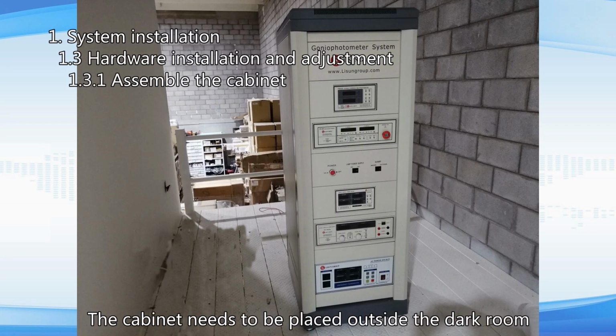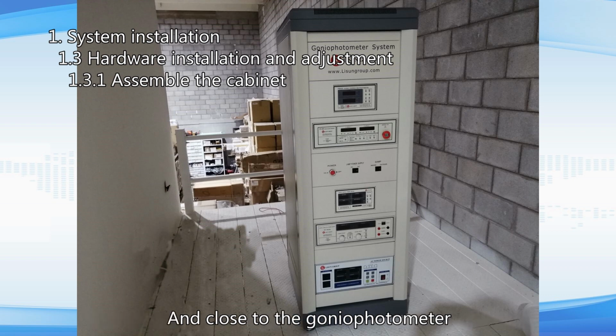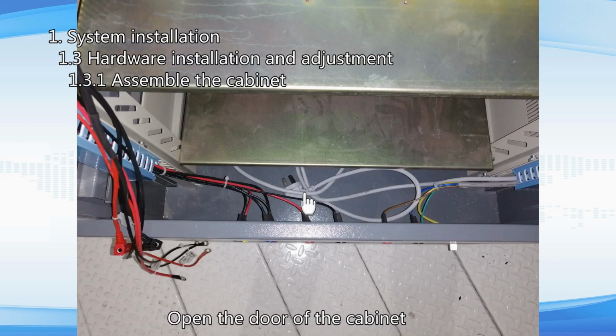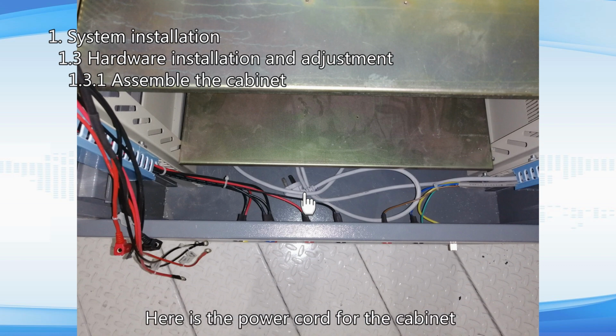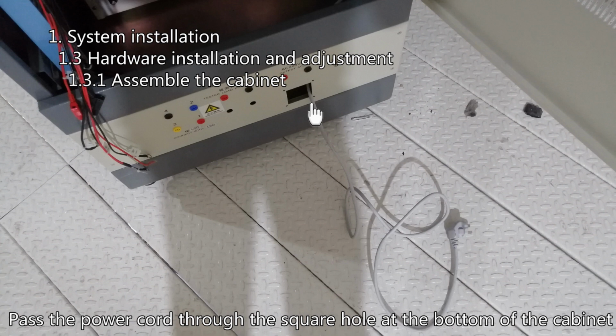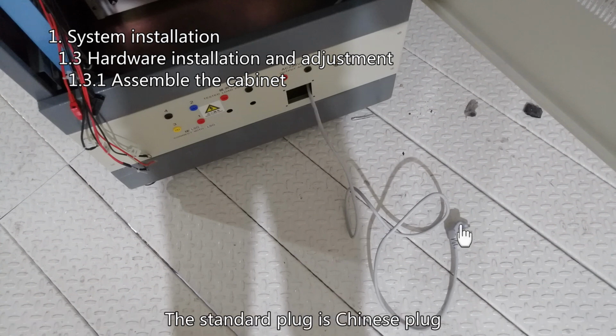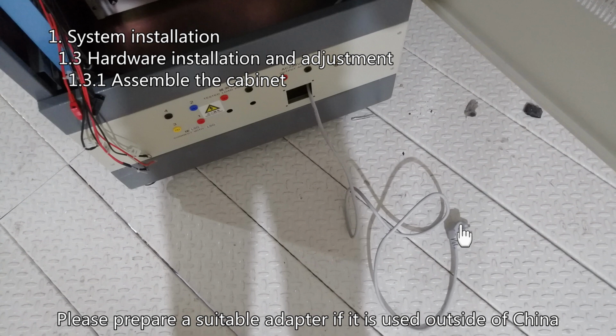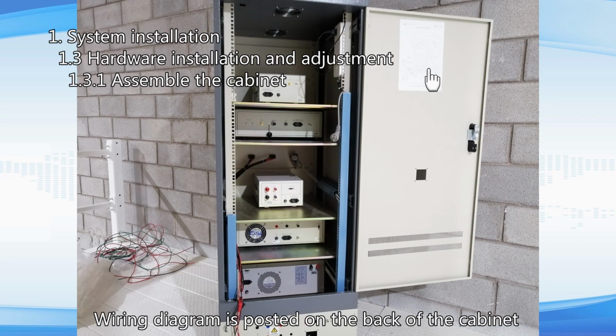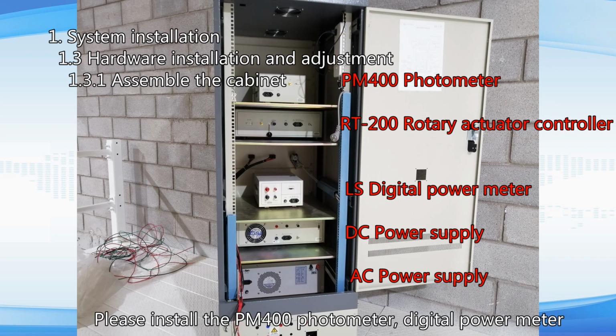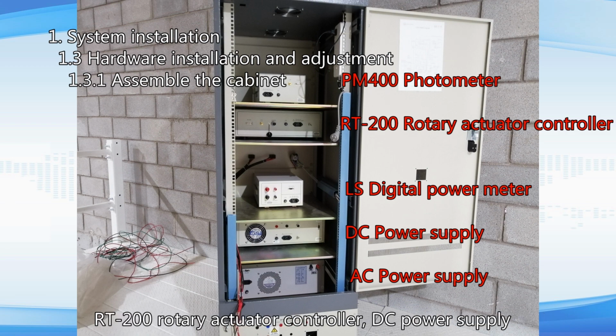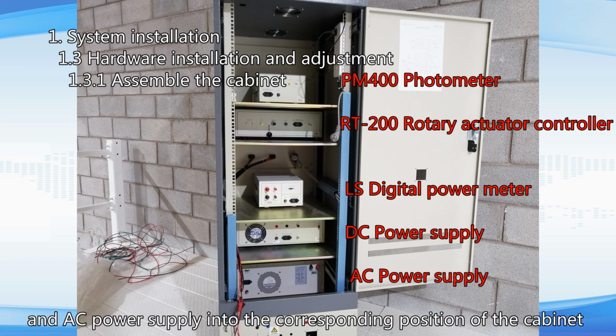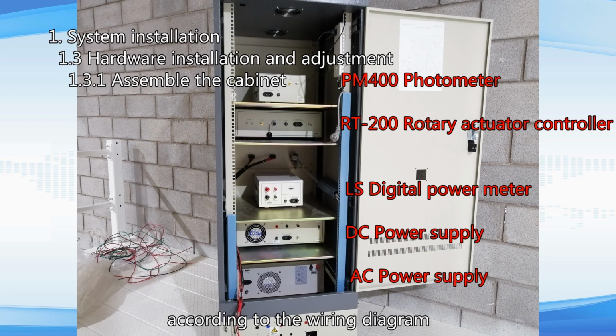The cabinet needs to be placed outside the dark room and close to the goniophotometer. Open the door of the cabinet. Here is the power cord for the cabinet. Pass the power cord through the square hole at the bottom of the cabinet. The standard plug is a Chinese plug. Please prepare a suitable adapter if it is used outside of China. The wiring diagram is posted on the back of the cabinet. Please install the PM400 photometer, digital power meter, RT200 rotary actuator controller, DC power supply, and AC power supply into the corresponding position of the cabinet according to the wiring diagram.